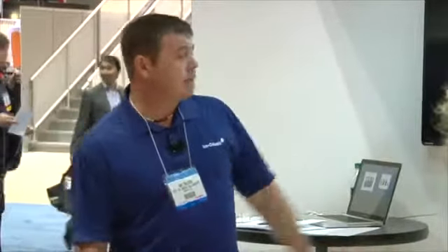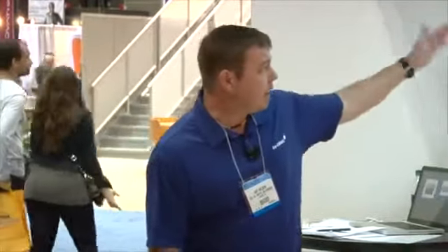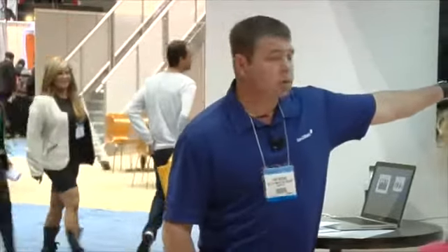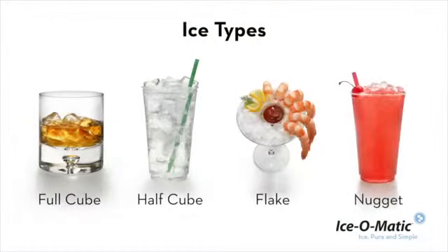They know that they have these lunch rushes that come in and they have their dinner rush. So what they're doing is putting these high capacity machines on top of these dispensers, because these are only going to store about 200 pounds of ice. That seems very overkill, to have a 1,500 pound machine on top of a 200 pound dispenser. But they're using that machine for the recovery ratio, so that way they can pick up their ice production.